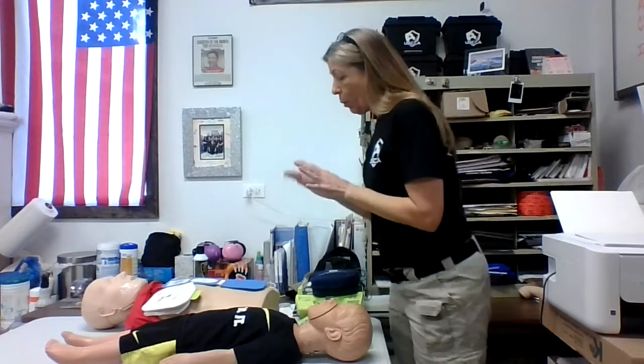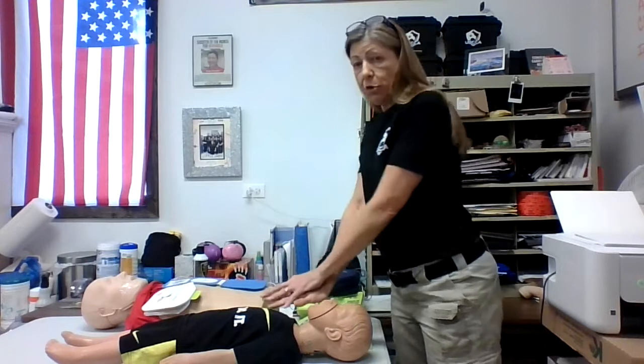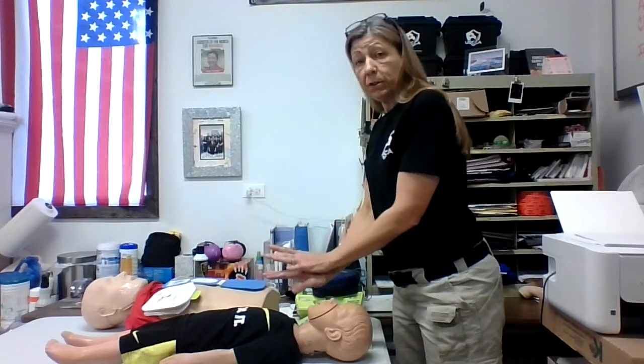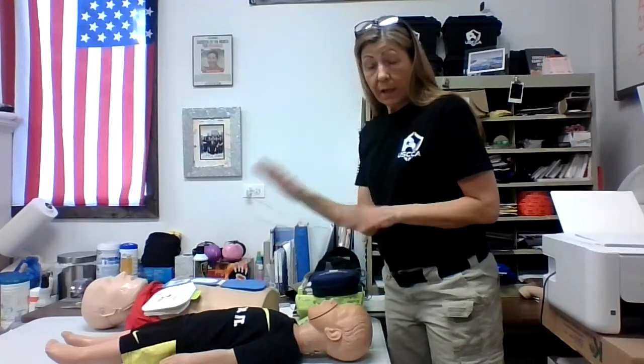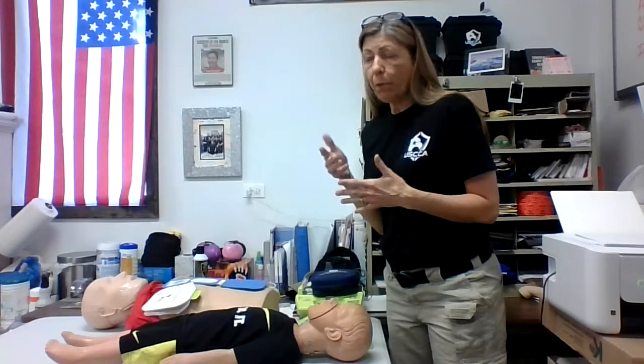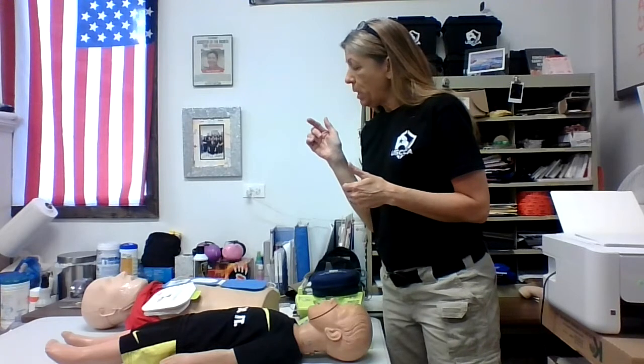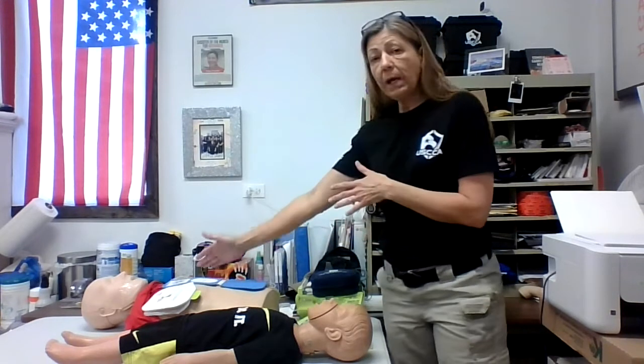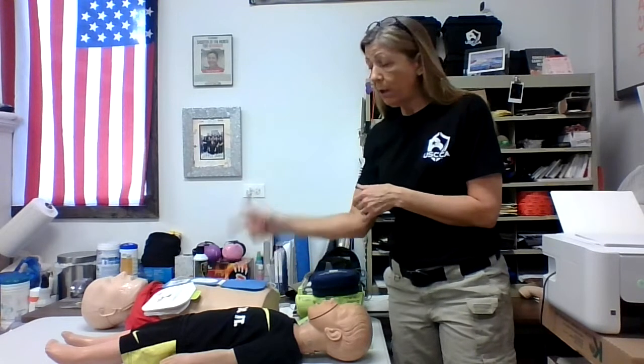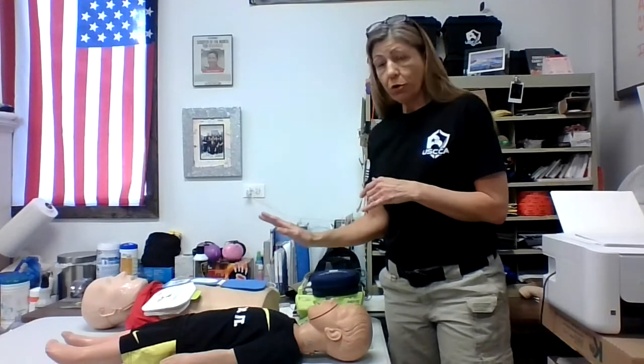No movement. What do I mean by movement? Well, let's say I'm doing my compressions on the patient's chest. That's movement. If the machine starts to analyze like an EKG does, looking at their heart motion, their rhythm, what's going to happen is it's going to see my compressions at the high rate of speed that we apply those now, almost 2 per second. That is simulating one of those 2 shockable rhythms. VTAC, we're pushing right up on it. This machine sees VTAC and it's likely going to say shock advised. Again, that keeps me from doing compressions on the patient that needed it. He's getting a shock that he didn't necessarily need. Complete waste of time. So make sure there's no movement.